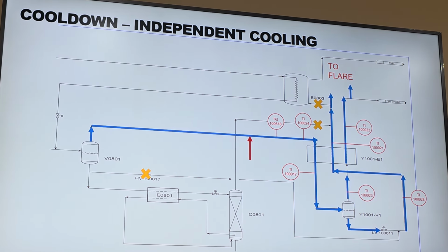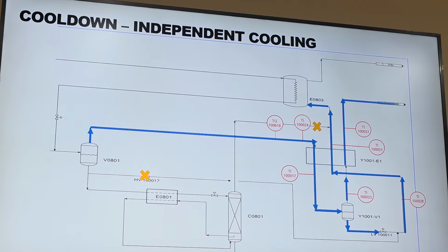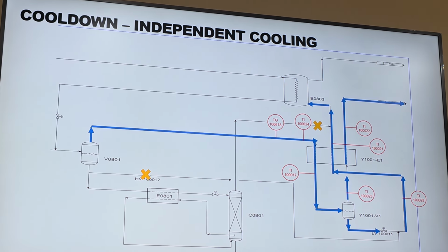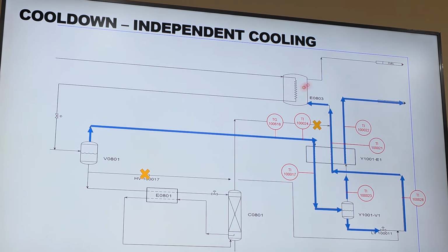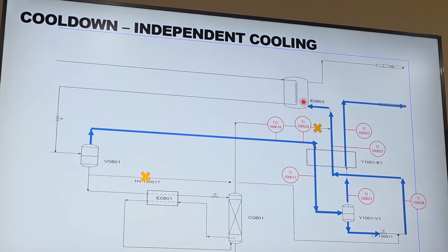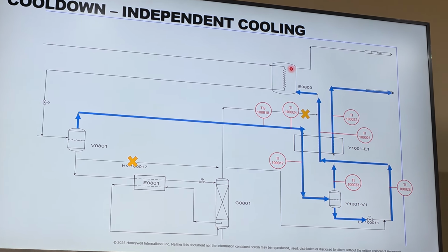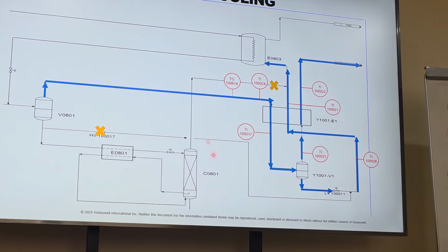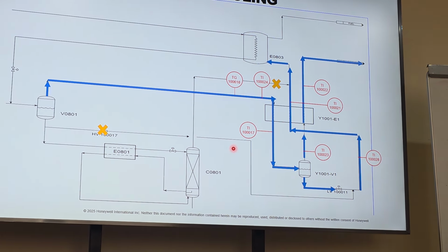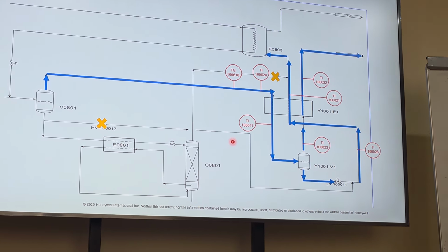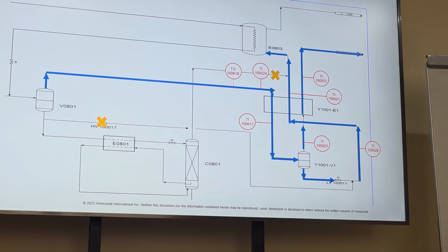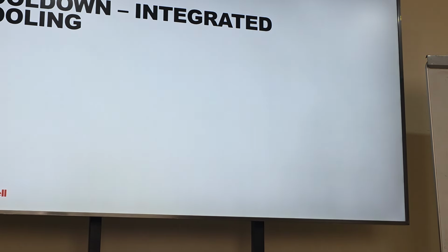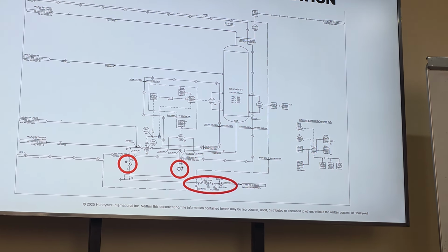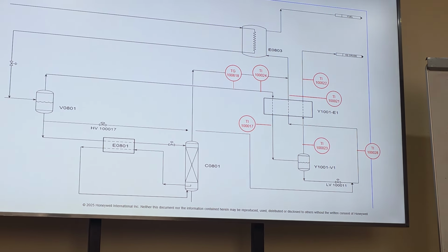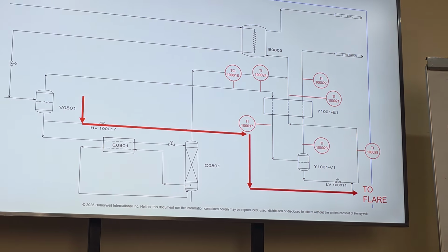And then once you get within 28 degrees C of your flash gas, you can begin flowing flash gas to the shell of E0803, blending it with the rejection column. Okay? So for the integrated case, the prep is all the same. We're going to sweep the line again.